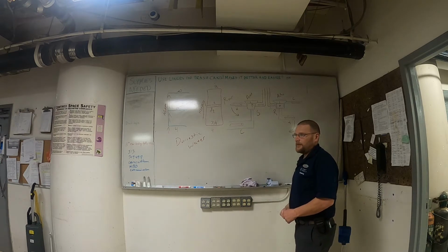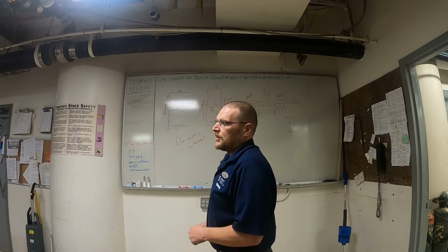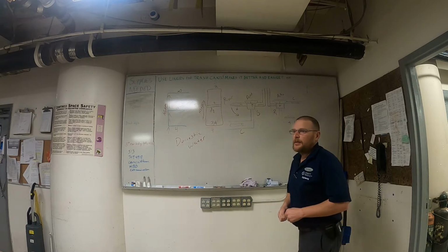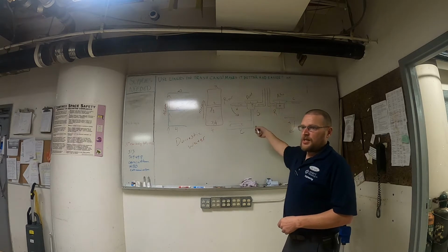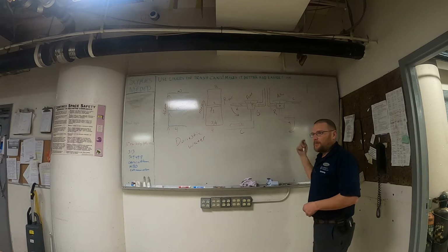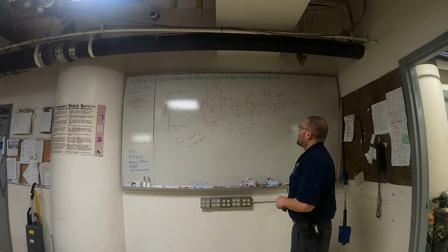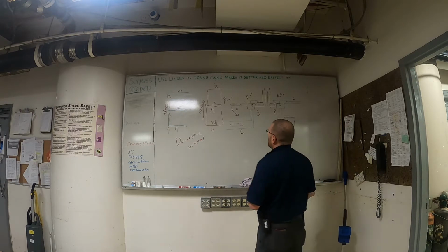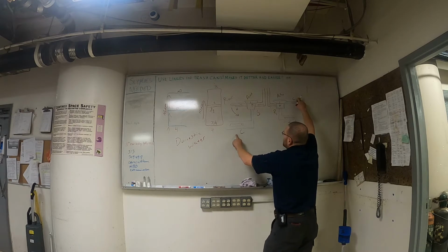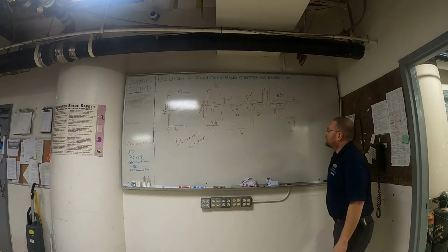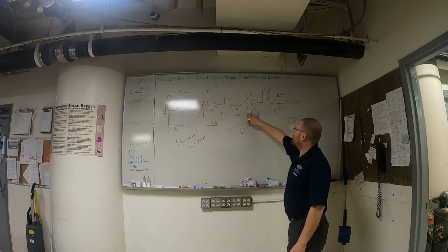Now, do I ever shut off all 4 valves? No. That will bring air into the system and it will cause your whole system to get airlocked. Then you have to go up on one of the higher floors, drain the unit, drain the air off the unit, pull the water back up to it. It's a whole big mess. You always do these in groups of 2, the 2 heating or the 2 cooling. You'll never open these 2 at the same time.